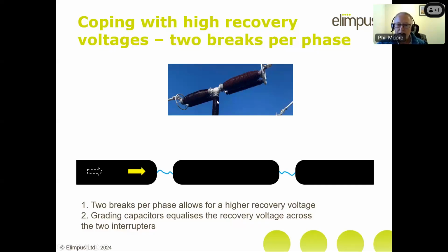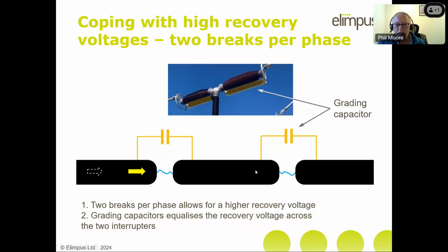The problem with that approach per se is that this middle point is in fact floating when the arc goes out, and that can sometimes lead to unequal voltage distributions across the contact gap. So it's more common to see a capacitor put across the contacts, which is called the grading capacitor, and you can see that in these. I've just highlighted that in orange. You can see it's bolted on parallel to the interrupter, and what that does is more or less guarantee that the transient recovery voltage is equal across the two gaps, so that they both work equally towards stopping the arc reappearing.